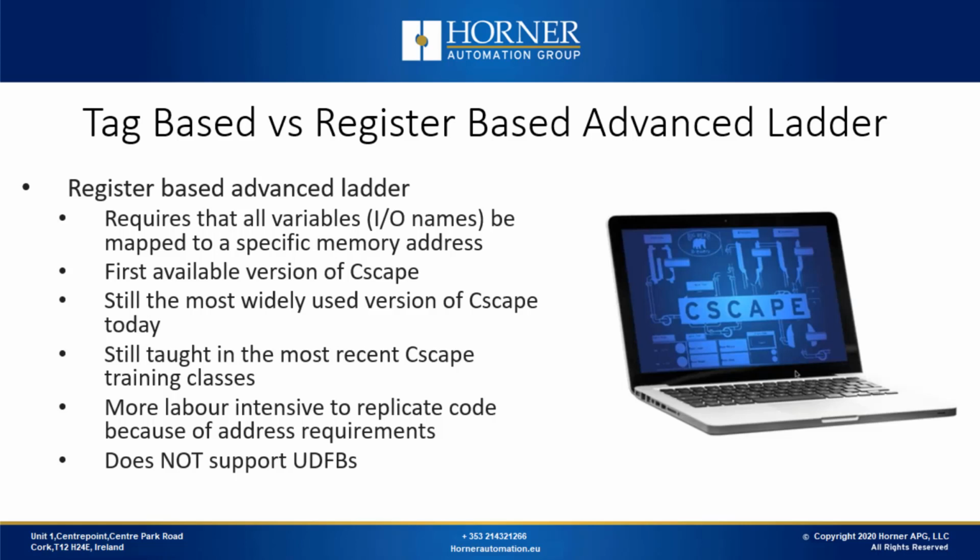It is the most labor-intensive when it comes to replicating code, because of the addressing requirements. So if you have a section of code that you want to replicate, for example, code for a pump, if you have several you want to use, you can easily replicate the logic, but you have to manually readdress the newly replicated code. Also, for similar reasons like the addressing, register-based logic does not support user-defined function blocks. User-defined function blocks are very powerful tools that allow you to efficiently reuse sections of your code.